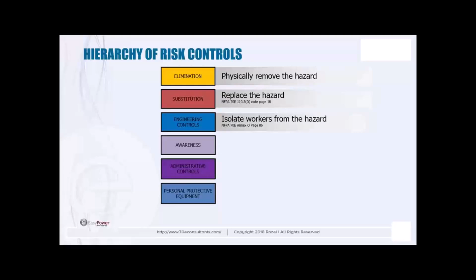First, let's talk a little bit about training. If we look at NFPA 70E, it talks about the use of the hierarchy of risk control, and training is one of the methods to reduce risk - it falls under awareness. The idea is effective training: if we perform training properly, when it's over, our employees should be able to go back into our facilities, identify the hazards they'd be exposed to, such as arc flash and shock, and understand what safe work practices they can incorporate to reduce that risk.